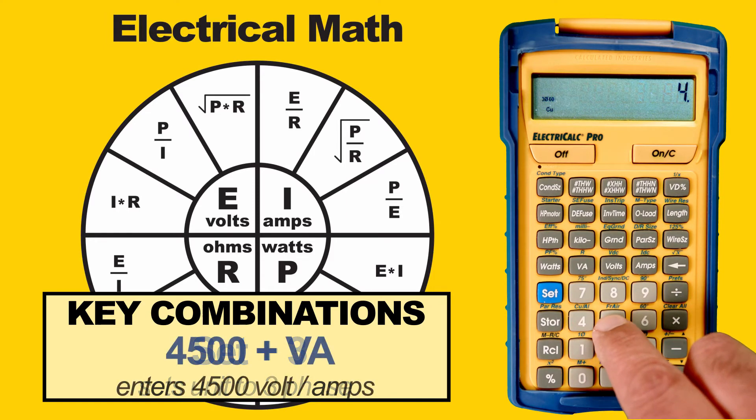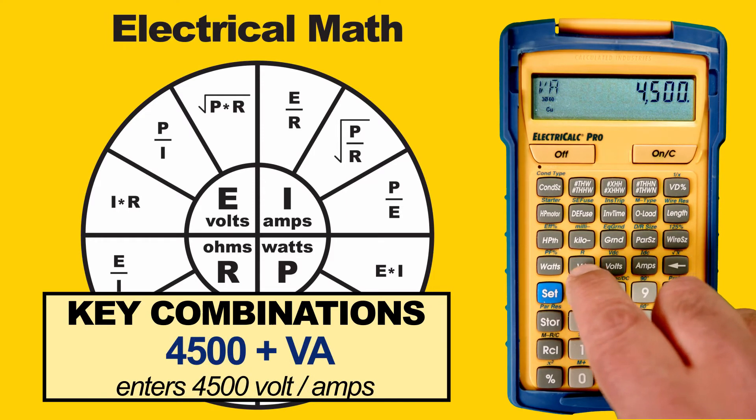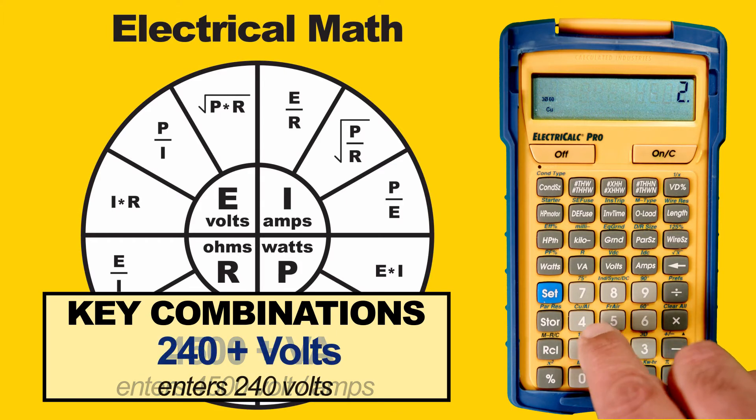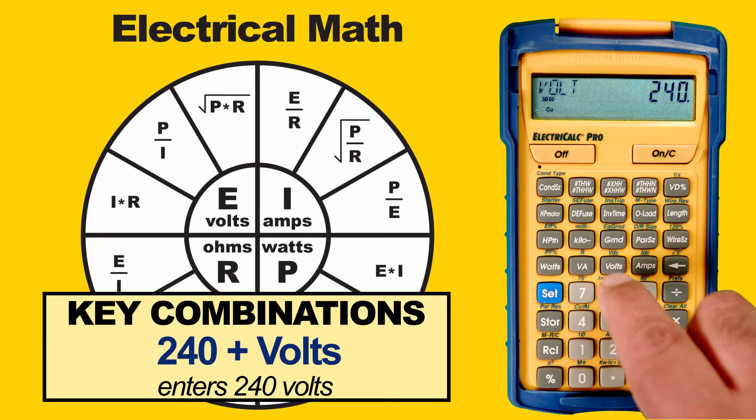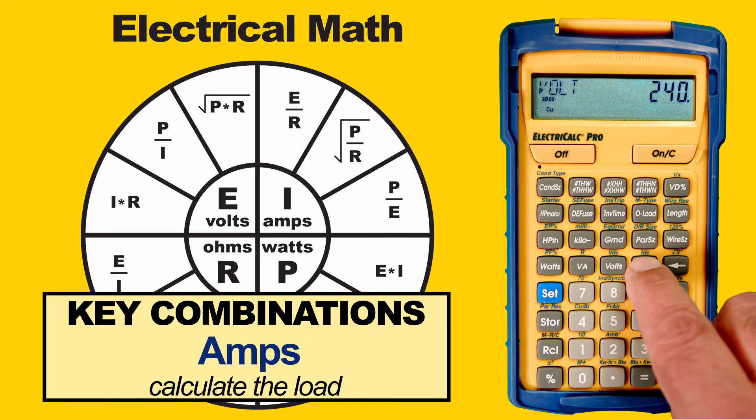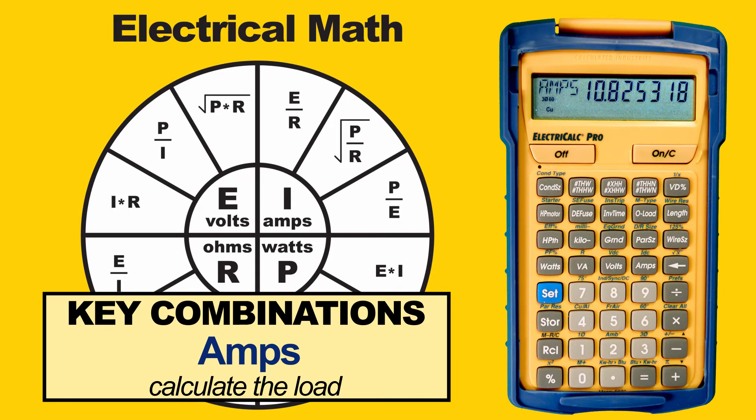We enter our Volt Amps, which in our example is 4500, and our Volts, which is 240. We can calculate our load by pressing Amps and we see that we have roughly 10.8 Amps.